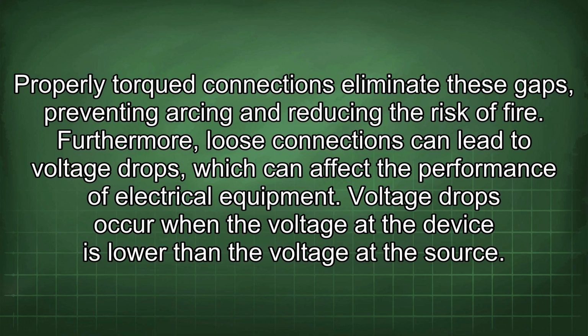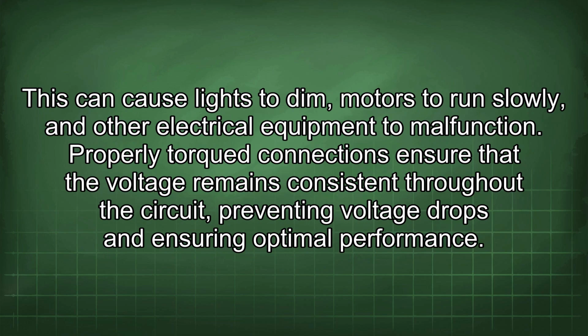Furthermore, loose connections can lead to voltage drops, which can affect the performance of electrical equipment. Voltage drops occur when the voltage at the device is lower than the voltage at the source. This can cause lights to dim, motors to run slowly, and other electrical equipment to malfunction. Properly torqued connections ensure that the voltage remains consistent throughout the circuit, preventing voltage drops and ensuring optimal performance.